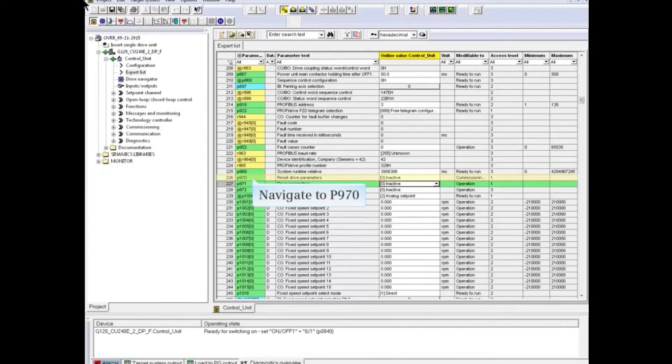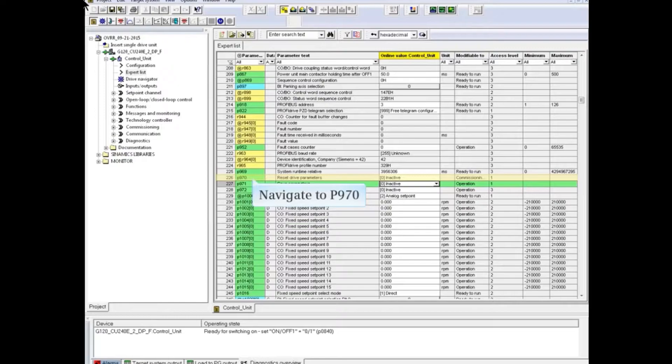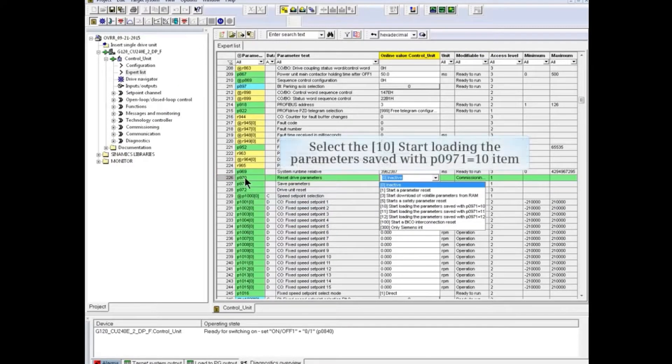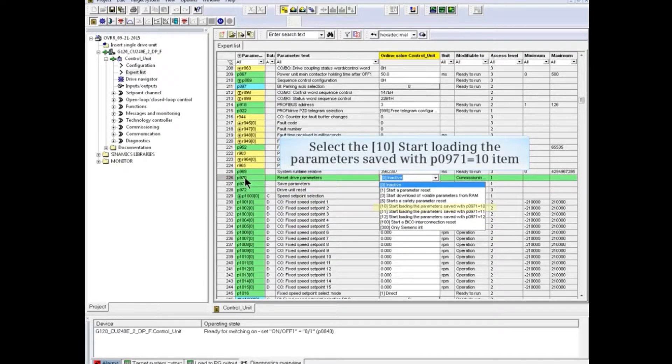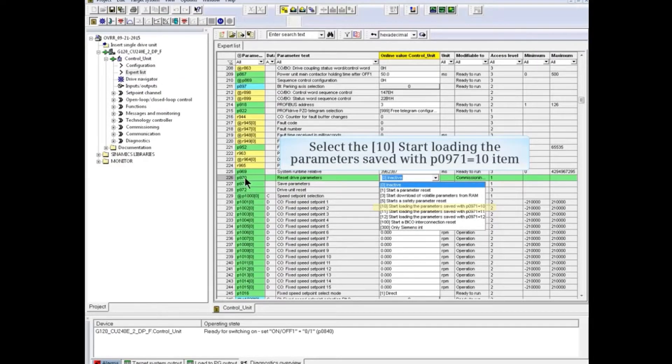Online with Starter, navigate to P970 in Expert List. From the drop-down menu, select number 10, start loading the parameter saved with P971 equals 10.